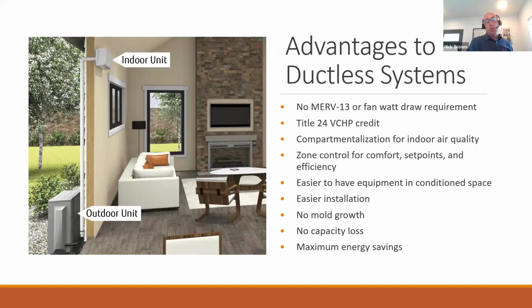Yeah, so as a retrofit, you either pull that piece of drywall off and run the drain down through the wall, or you punch out next to the refrigerant lines and you run that down the wall to the exterior landscaping. That's what I'm seeing in my neighborhood. A lot of these outdoor units up on racks attached to the wall where there's not room down on the ground, and just draining out to landscaping. Or Nick, we're seeing a lot of, if there's multiple high walls on the same, let's say the second story, they will all come to a home run together, and then they'll pump all the units out at one time. I see. We've also seen in this application where it just runs along the refrigerant line, and they'll put an outdoor condensate pump if they need to get it somewhere else.